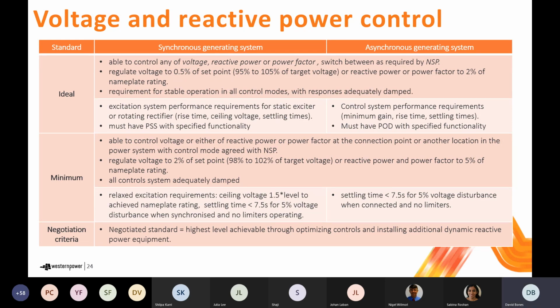You'll see that on this slide, we've got elements of both the ideal and minimum standard expressed differently depending on the technology. If you've got a generating system that's a combination of both synchronous and asynchronous generating systems, then the rule of thumb is really the synchronous part needs to meet the requirements for synchronous generating systems, and the asynchronous part needs to meet the requirements for the asynchronous generating systems. And as a whole, the common requirements need to be met.